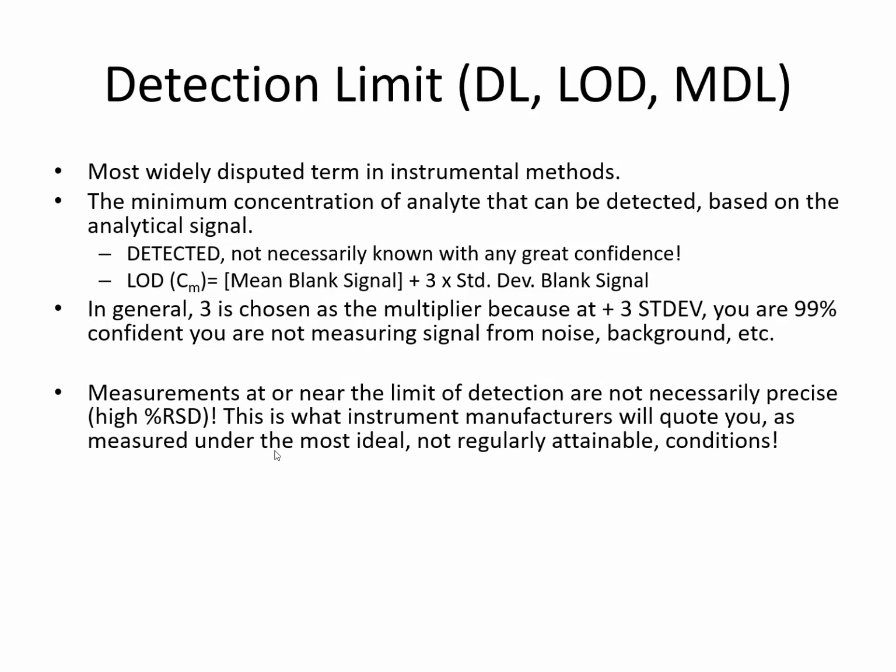And measurements at or near the limit of detection are not necessarily precise. So they have a high percent RSD, relative standard deviation.